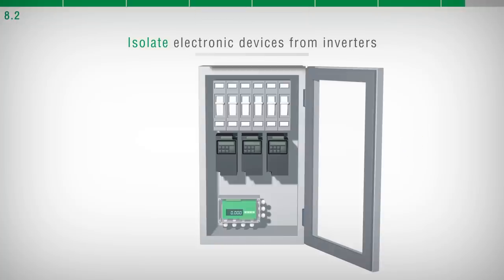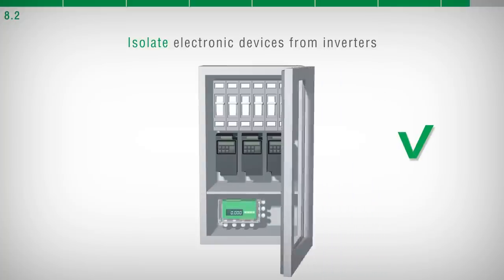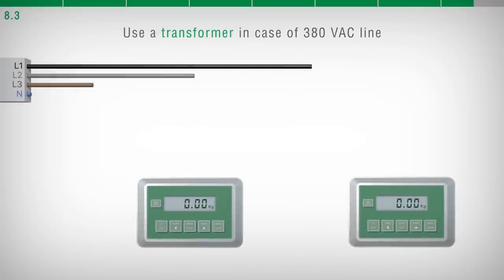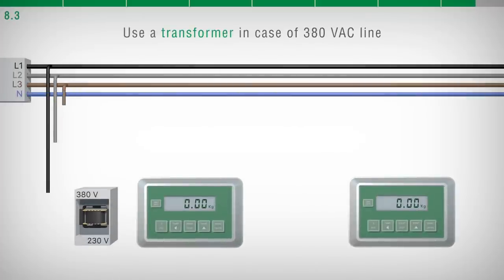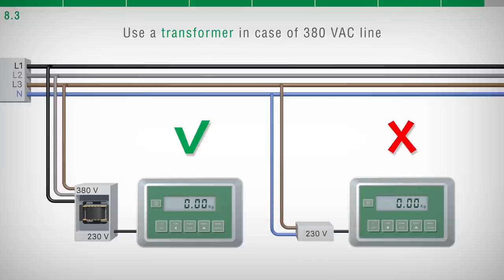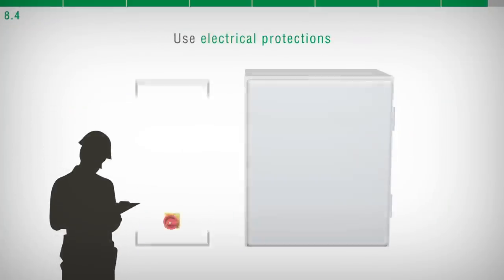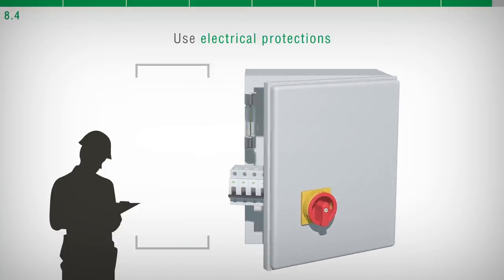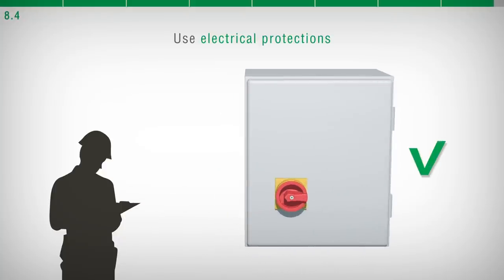However, if this cannot be avoided, install special filters and insert separation plates between the inverters. In case of power supply 380 VAC, a 380 to 230 VAC transformer must be used. Do not use a 380 VAC phase and the neutral one. The person in charge of the electrical panel must prepare and install all the electrical protections needed to ensure the safety of the plant.